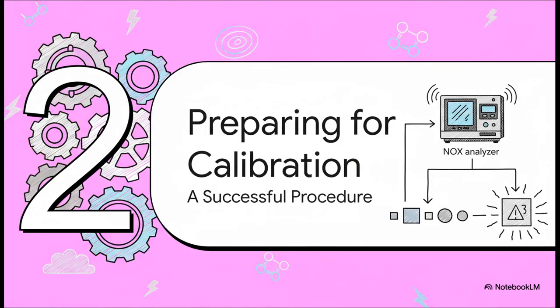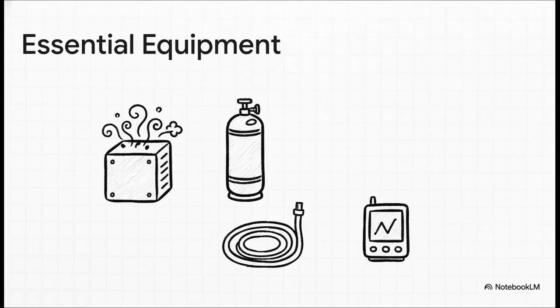Okay, so the stakes are pretty high, right? That means you can't just wing it. Getting your prep work done right is like 90% of the battle for a perfect calibration. Before we even think about touching the analyzer, let's get our gear lined up. You're going to need a source of zero air, that's for our baseline. You'll need a certified span gas, that's our reference point. And you need the right tubing, either Teflon or stainless steel, because you can't have any contamination. Oh, and a data logger? It's optional, but trust me, you'll want one for keeping good records.